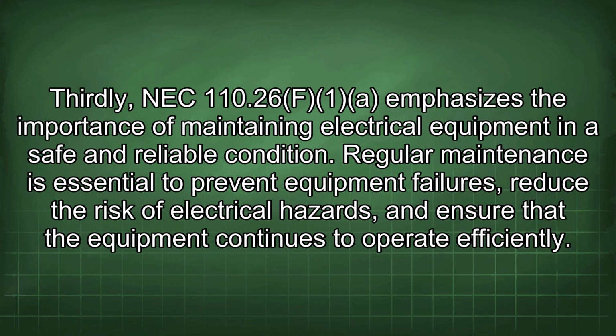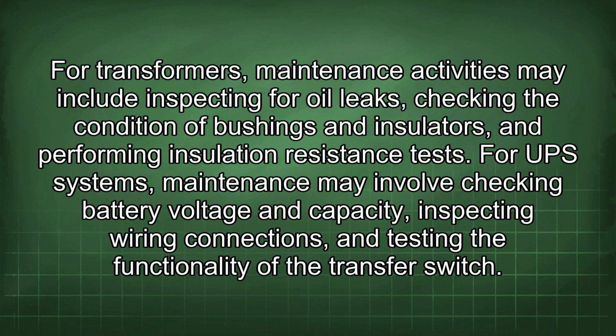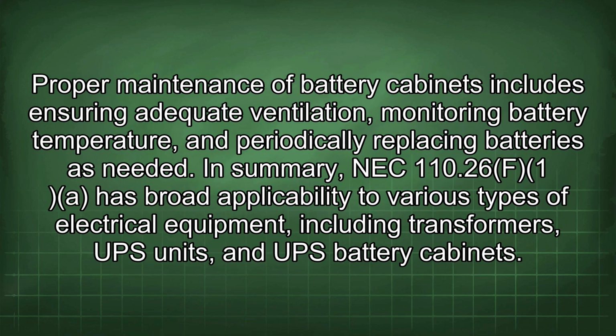Thirdly, NEC 110.26 emphasizes the importance of maintaining electrical equipment in a safe and reliable condition. Regular maintenance is essential to prevent equipment failures, reduce the risk of electrical hazards, and ensure that the equipment continues to operate efficiently. For transformers, maintenance activities may include inspecting for oil leaks, checking the condition of bushings and insulators, and performing insulation resistance tests. For UPS systems, maintenance may involve checking battery voltage and capacity, inspecting wiring connections, and testing the functionality of the transfer switch. Proper maintenance of battery cabinets includes ensuring adequate ventilation, monitoring battery temperature, and periodically replacing batteries as needed.